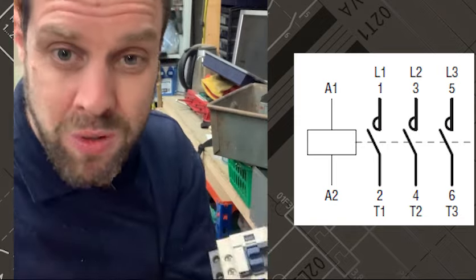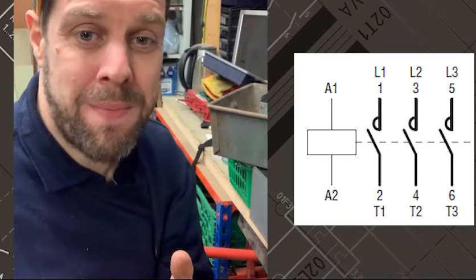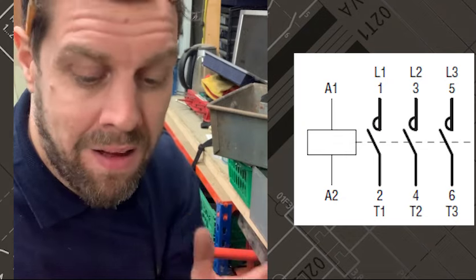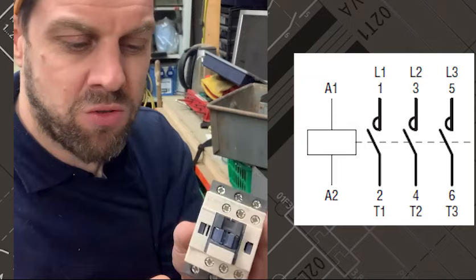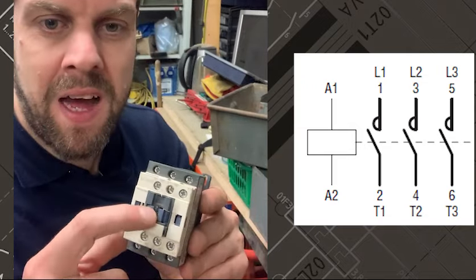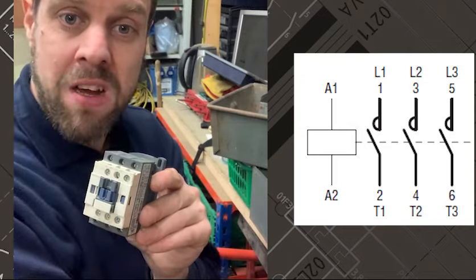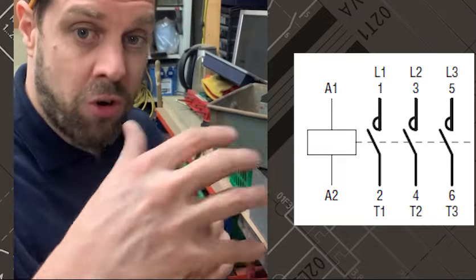Then you put the contacts in here that are big that run the motor or something and it will switch it. It is that simple. Think about it: say you've got three million lights and you can't turn them on with one light switch. You make your one light switch switch the coil on, and then you put as many contacts as you need to switch on all your lights.